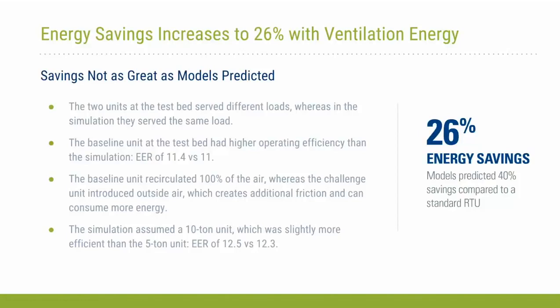So all of these lead to some differences in the estimate of simulated savings versus what we saw in the field. We saw a savings of 26%. The 16% number you saw was the difference in the seasonal energy efficiency ratio. But in terms of energy, it was a 26% reduction of energy for the high performance unit compared to the standard unit. The simulations predicted it would probably be around 40% for that climate location and for that type of building. Next slide, please.